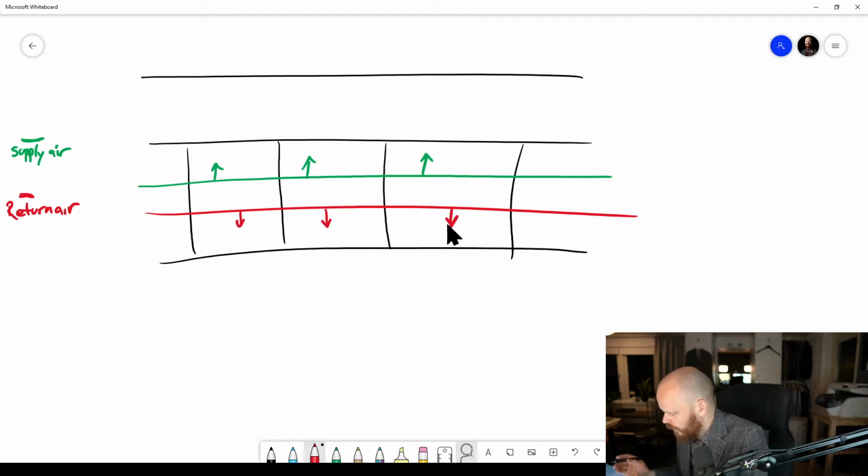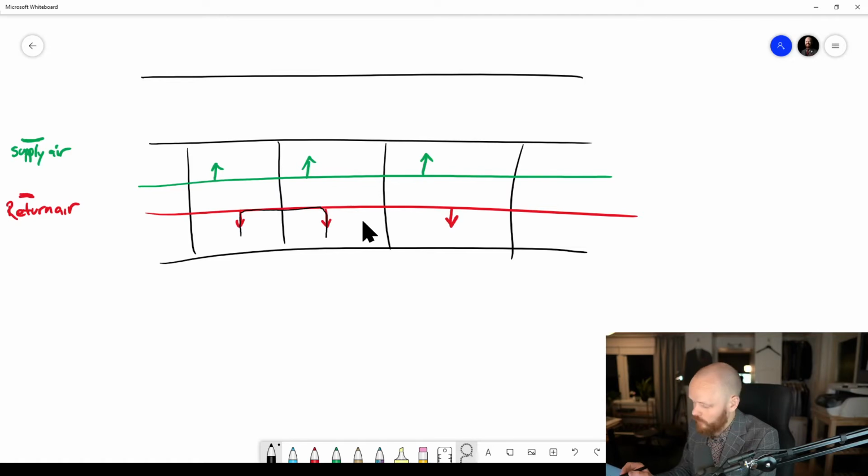Now, there are some risks involved with this with regards to acoustics, because if you do it like this, there's a higher probability that you could get sound transmission problems when sound enters these ducts and comes out into the next room. It's the shortest possible path. It's also sensitive, because the pass-through of the wall needs to be properly done so there's no leakage, and it's more sensitive to workmanship issues.